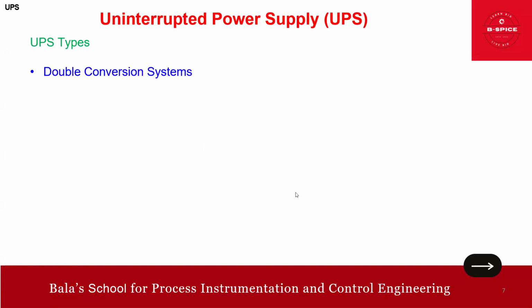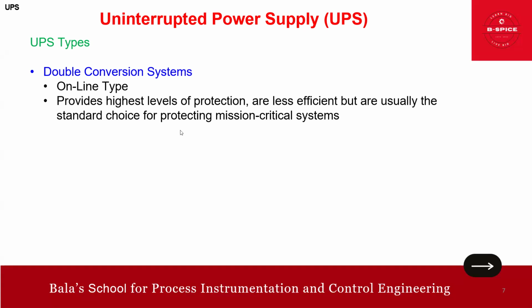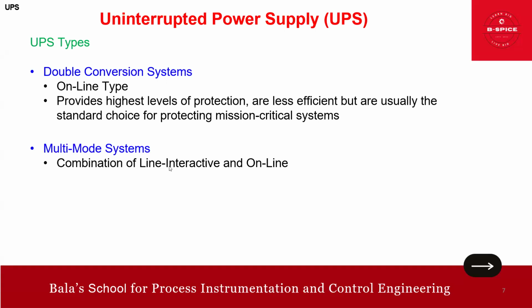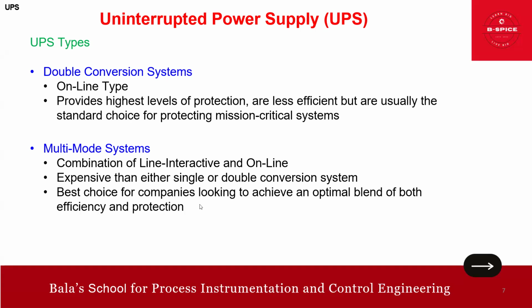This is about single conversion. Now the double conversion type, I'm only focusing on the concept, I'll explain the details in subsequent slides. In double conversion we have an online type. It provides a high level of protection, as I highlighted earlier, but is less efficient, and is usually the standard choice for protecting mission critical systems. Then multi-mode, which is nothing but a combination of line interactive and online. It's more expensive than either single or double conversion because it's a combination of both, and it's the best choice for companies looking to achieve an optimal blend of efficiency and protection.